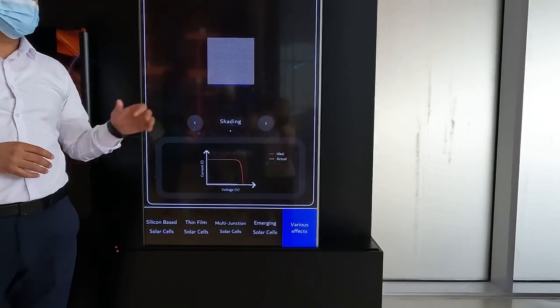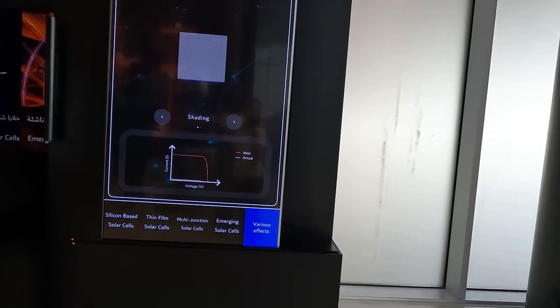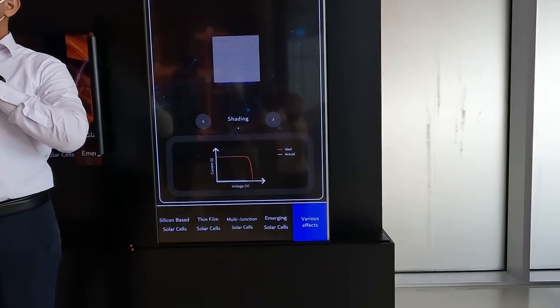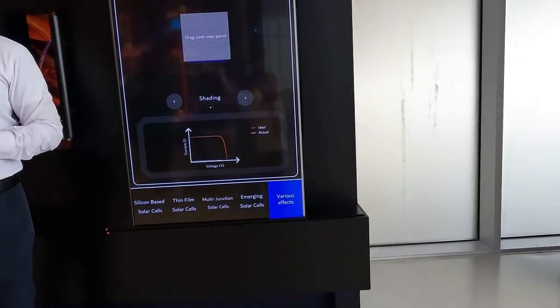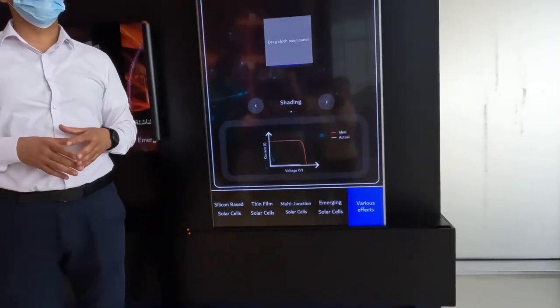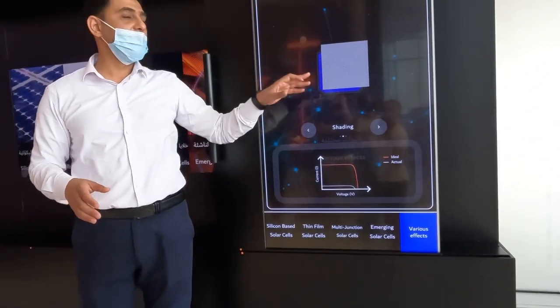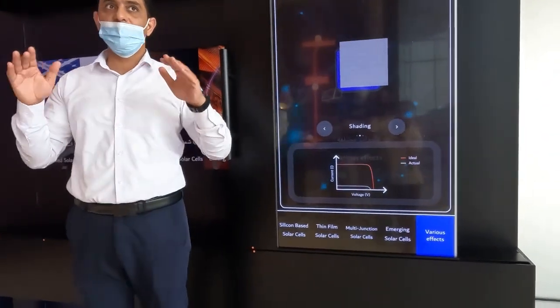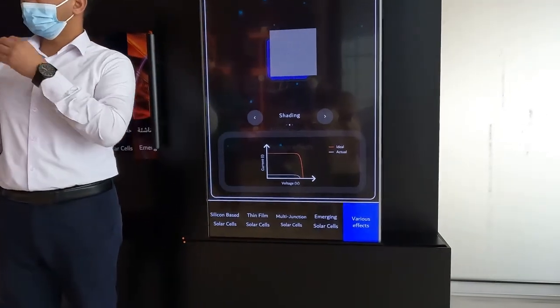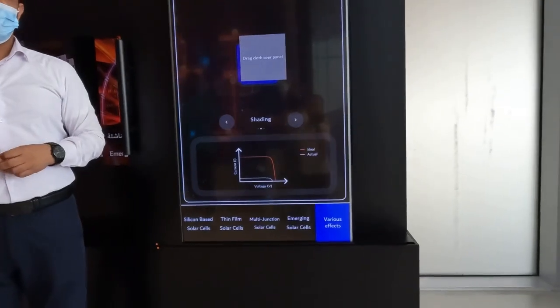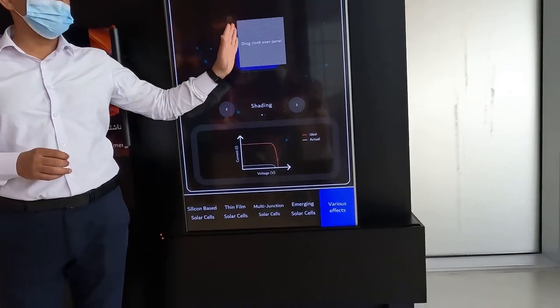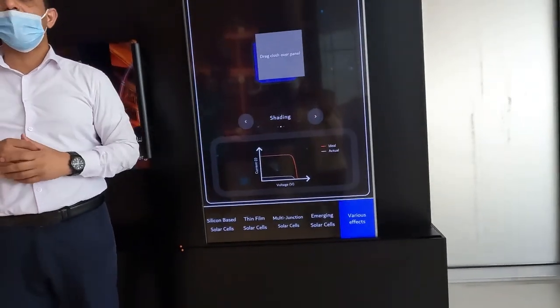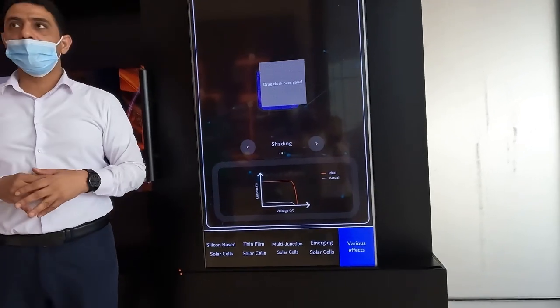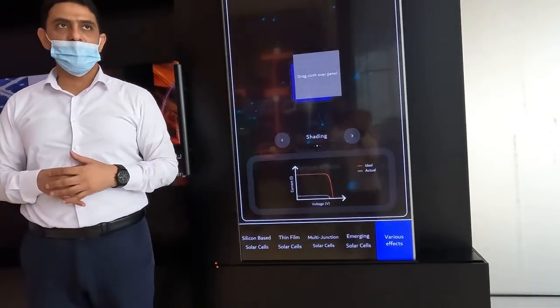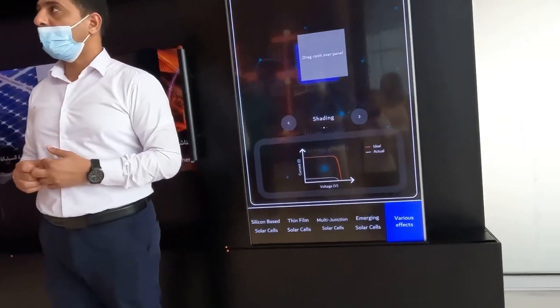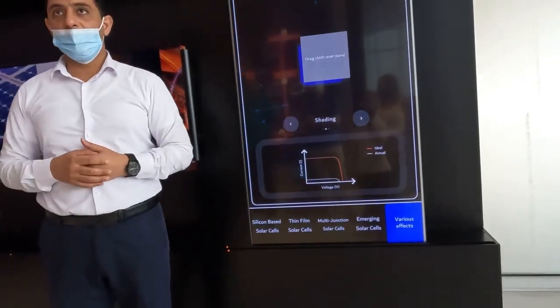Another very challenging problem is the shading issue. In this region, shading comes from sandstorms, especially in summer, when we have humidity at night followed by sandstorms. The sand sticks on the solar panels creating shade, so efficiency drops badly. Due to that, we started using robots that move to wipe the sand off, mostly at night. We clean the solar park here once every 7 to 8 days, but during a sandstorm we might clean it every 3 days.